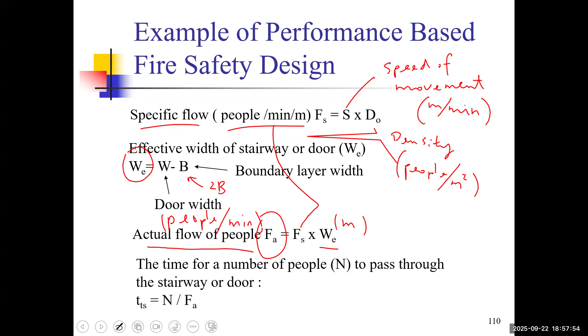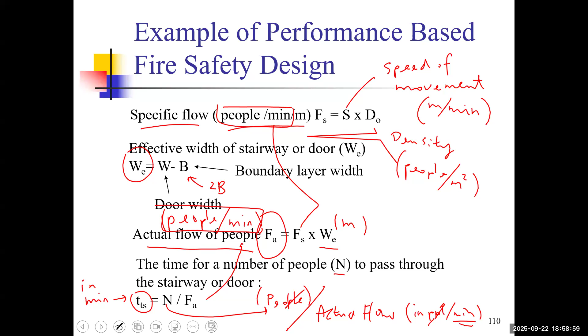Now the time for a number of people N to pass through the stairway or door is TTS. N is the number of people divided by FA, which is the actual flow. So the people divided by people per minute. So we have minutes as the final unit. Because N is in units of people, FA is in people per minute, so the people is cancelled out, and then you have the minute as the unit for TTS.